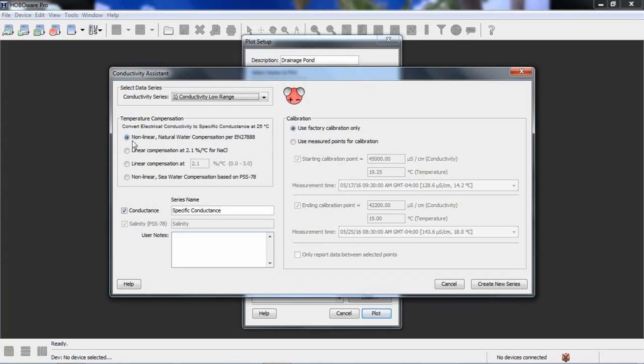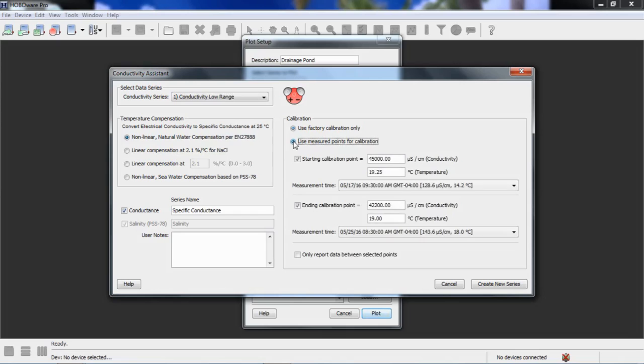We can see we just logged the low range, and we have the temperature channel here in degrees F. I'm going to switch that to degree C just for clarity, and we want to process that running the conductivity assistant. So we're going to click process. We want to select for our temperature compensation, we're going to select nonlinear natural water compensation, which is for fresh water. We're also going to choose to create the series called specific conductance.